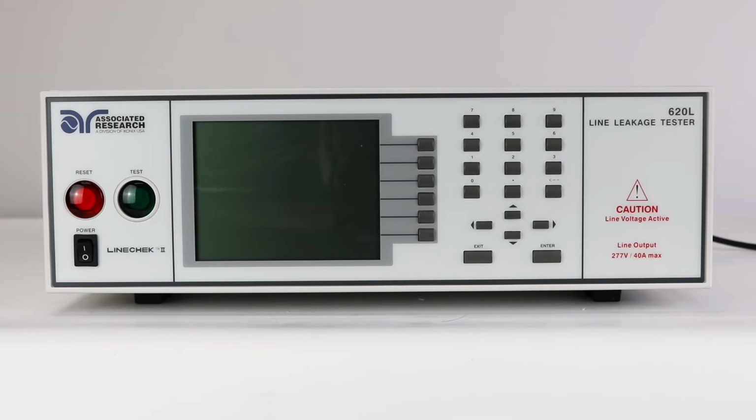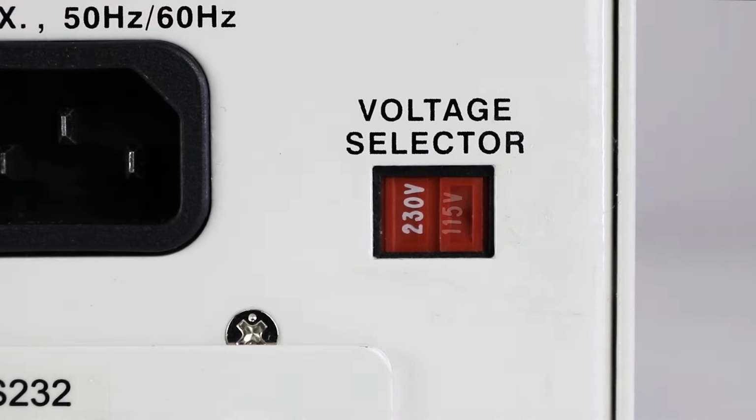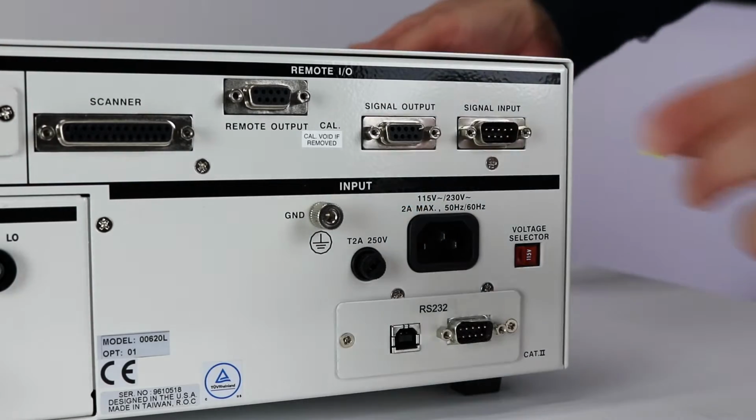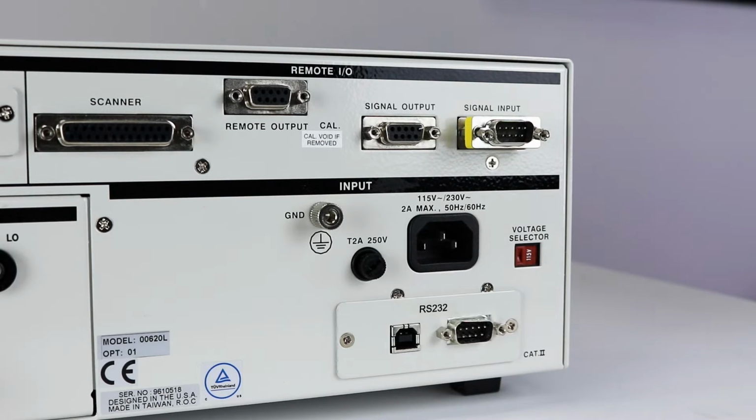First, you'll need to power up the linechek instrument. Check to be sure the correct input line voltage has been selected on the rear panel, either 115 volts AC or 230 volts AC. You'll also need to insert the remote interlock key into the signal input terminal on the rear panel. The instrument will not output voltage unless you use this key.